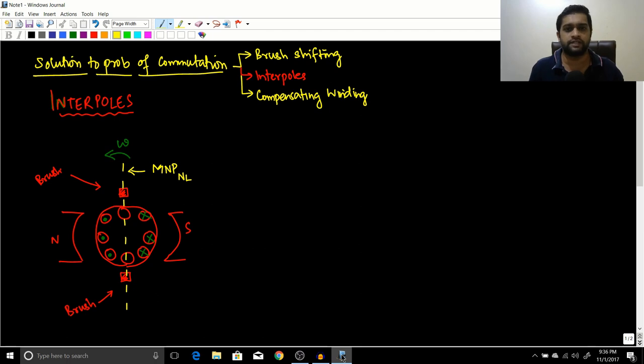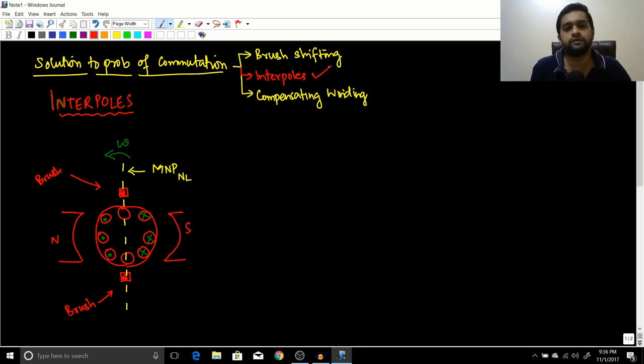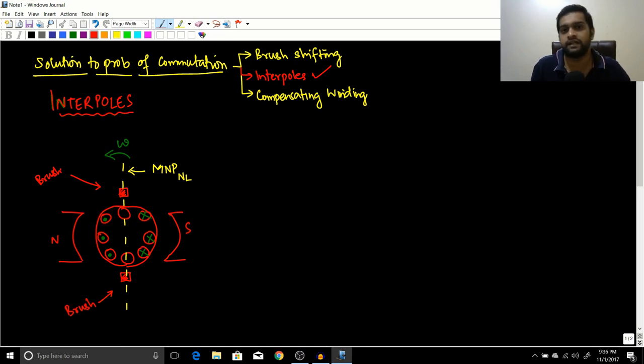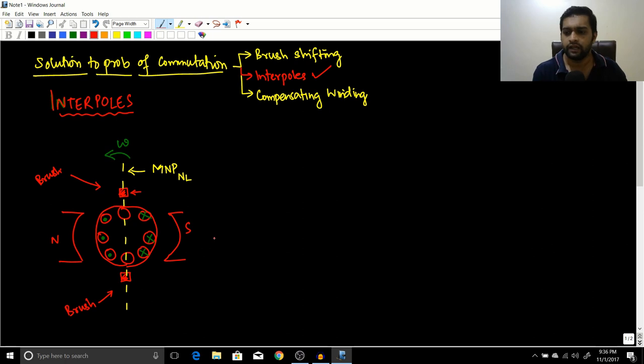The brush shifting method was not effective because somebody had to continuously change it — we took the example of Rahul who had to continuously do that. The solution should be built into the machine. The interpole solution is basically a constructional feature of the DC machine, so there is no requirement of anyone to shift the brushes. The brushes will remain at their fixed position.